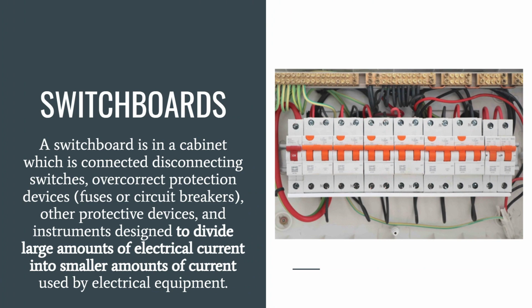A switchboard is a large cabinet or assembly of metal cabinets in which are connected disconnecting switches, overcurrent protection devices like fuses or circuit breakers, other protective devices, and instruments designed to divide large amounts of electrical current into smaller amounts of current used by electrical equipment. It contains one or more devices that can be used to disconnect a circuit from its power source both manually and automatically. Switchboards are the most powerful components of building distribution and protection systems. They are normally floor-mounted and rated for currents ranging from 1,200 to 6,000 amperes and voltages less than 600 volts. A switchboard is typically accessed from the front and back of the switchboard cabinet.